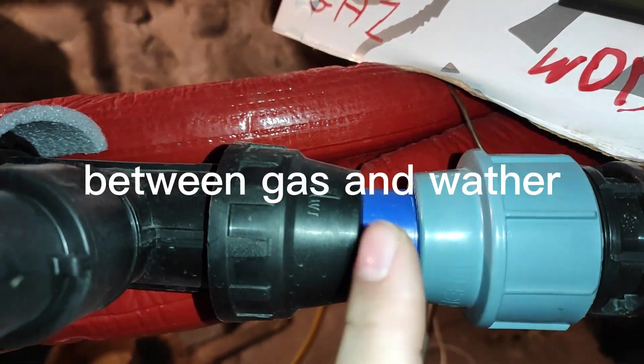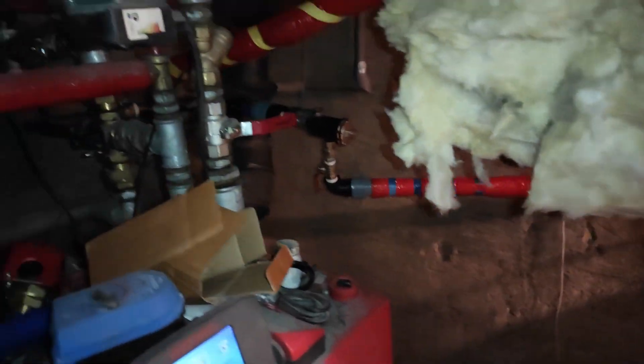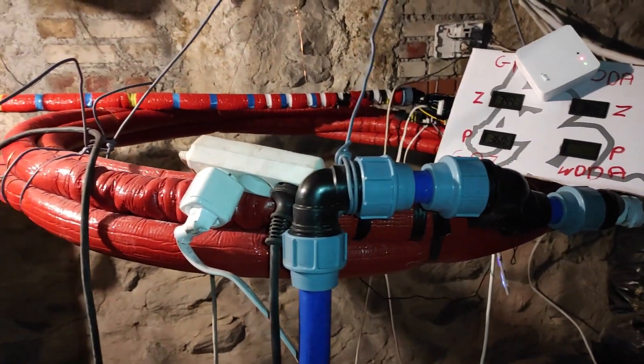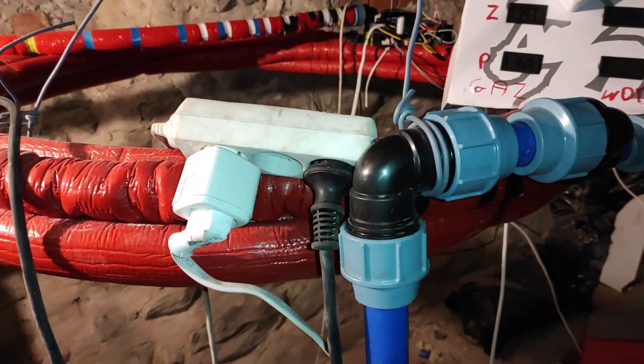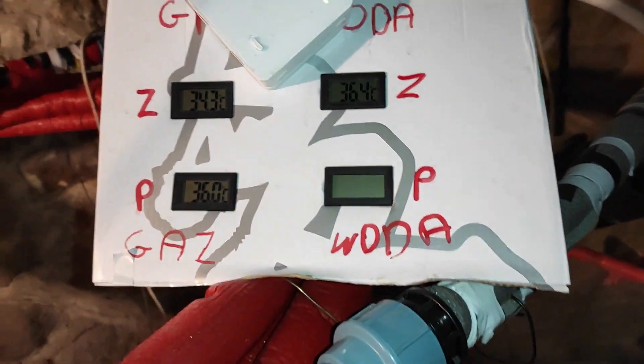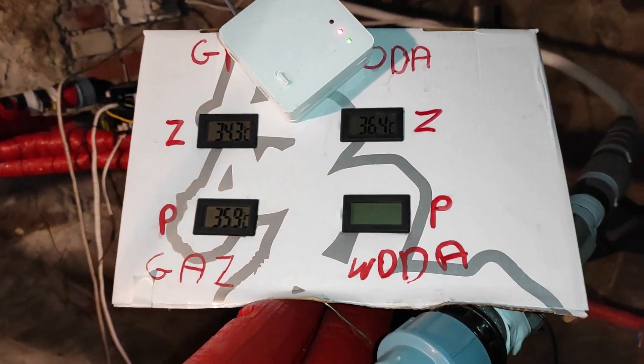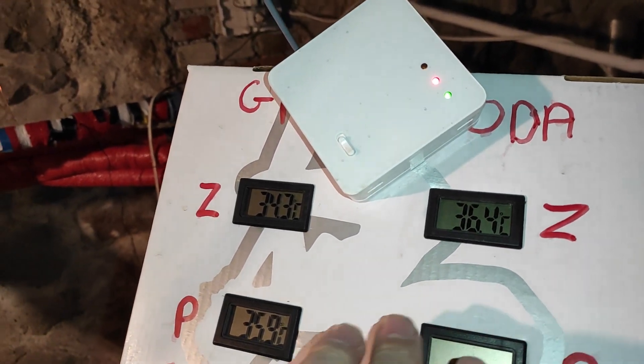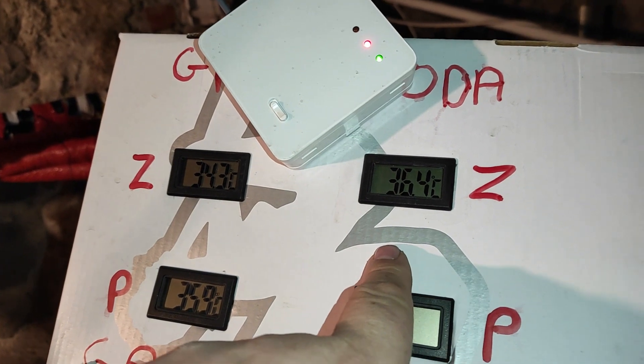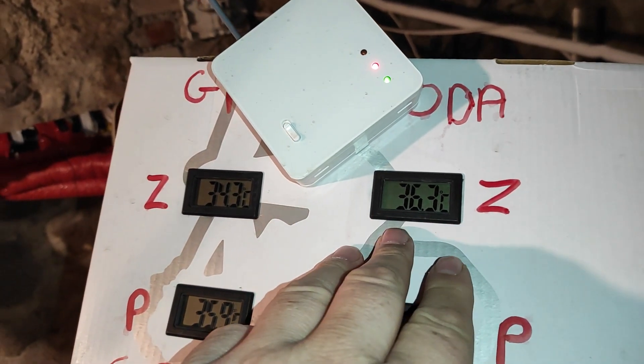The heat transfers from the gas to heat the water, and that water goes all the way through the heating system in the house, so you get warm water to heat your floor heating — as a heat pump normally does. It's running very slow now, getting 36 degrees right now because it's quite warm outside. I don't need more temperature, and although I have radiators rather than floor heating, it's only used upstairs where it's quite warm, so that temperature is enough for the radiators.